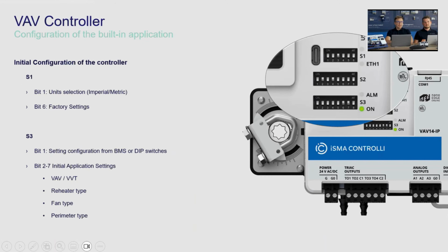We've got 6, 8, 8, and 4, and 6. So we've got 22 DIP switches available in the controller, and we can configure all the parameters available. So by the factory, you can select the unit, and then you can select all the types of the application that you described. We can choose between the VAV and the VVT system. We can select the type of heater that we have in the installation. We can select the type of fan that we have in the installation and the type of perimeter which we have in the installation.